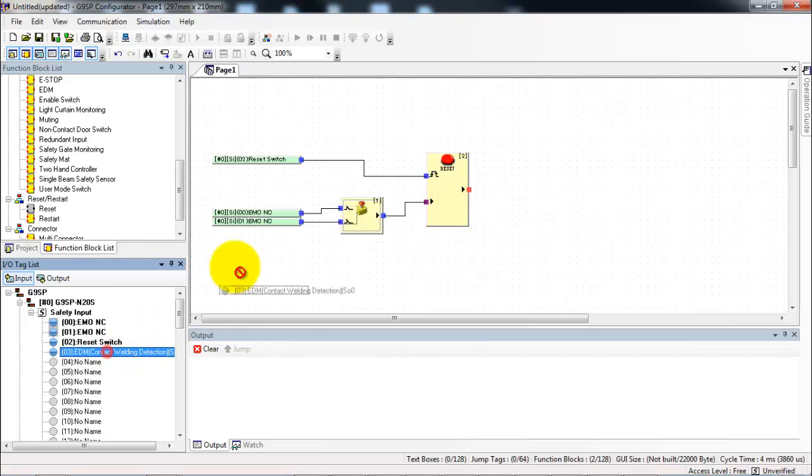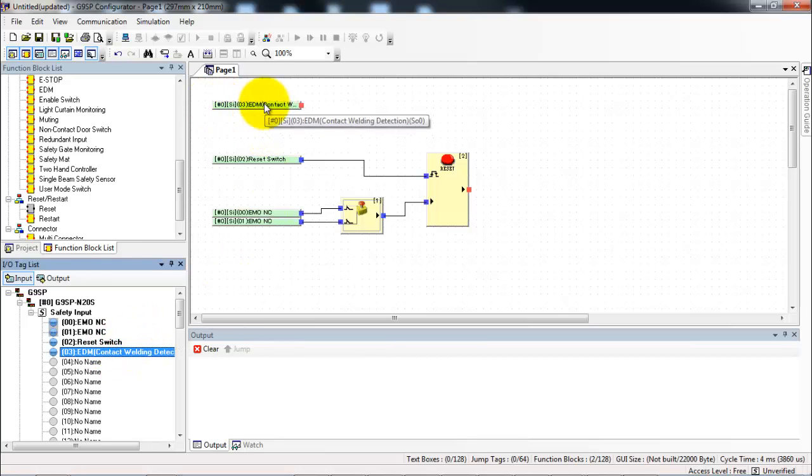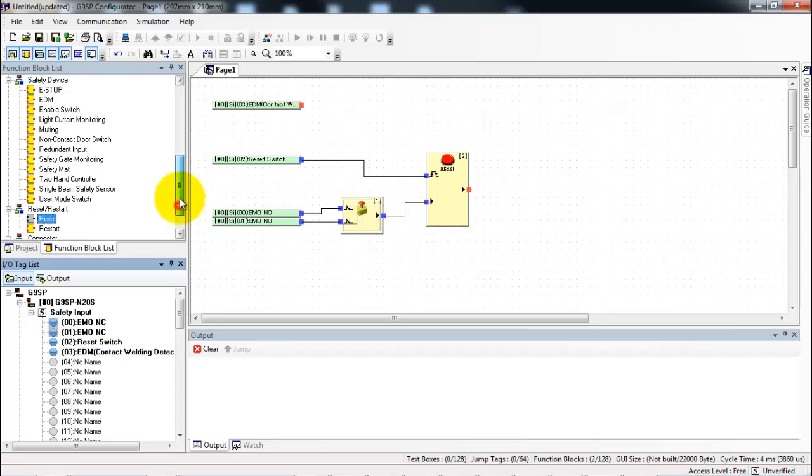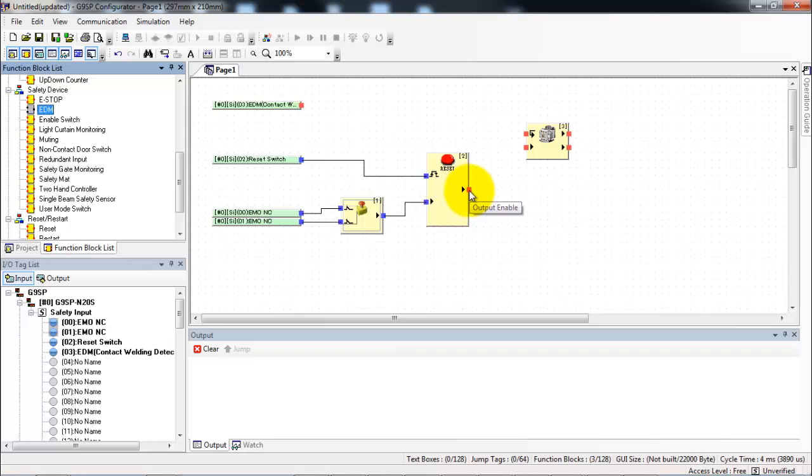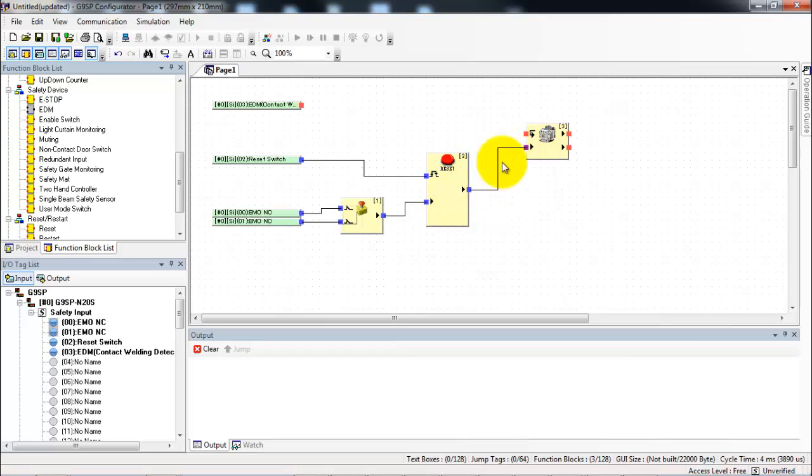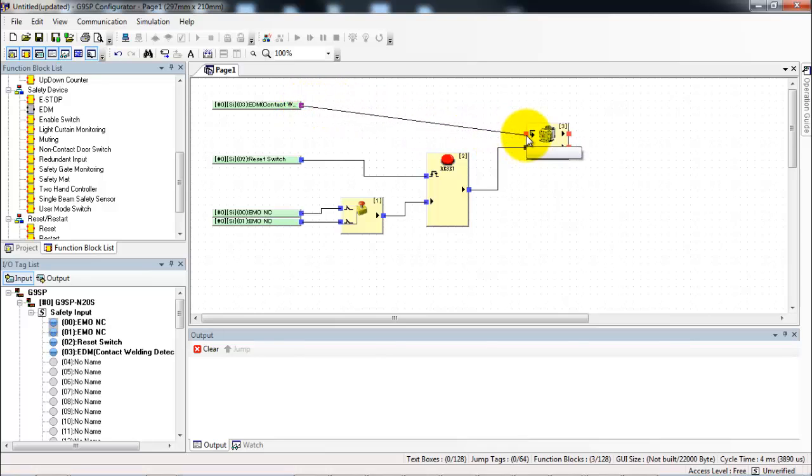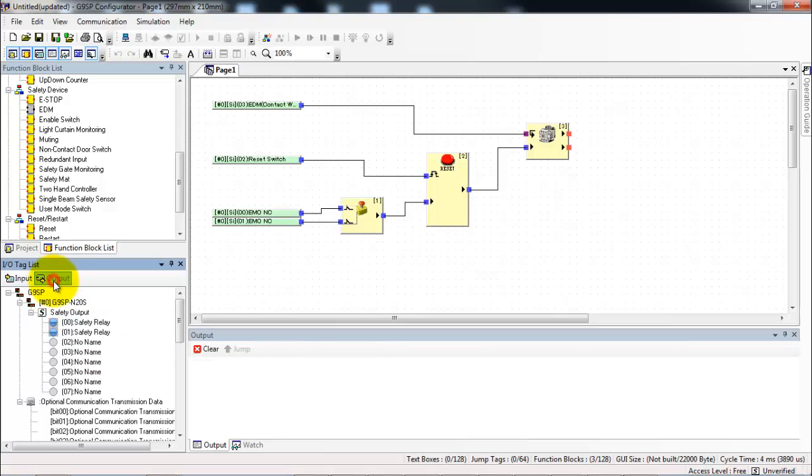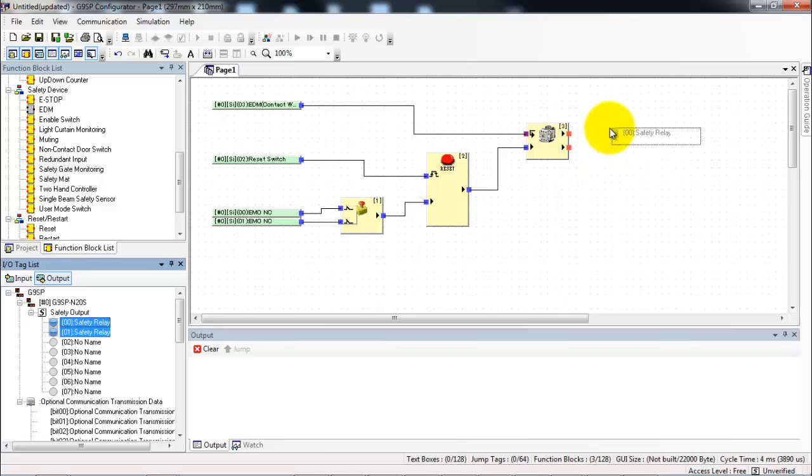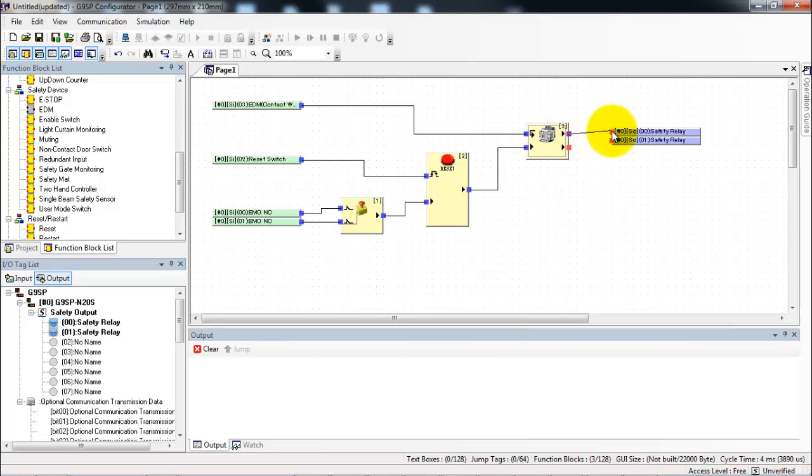Lastly we need to do our weld check. So I drop in my EDM contact and I grab the EDM function block. It stands for external device monitoring. Create a wire from the reset to the EDM and from the EDM input to the function block. Lastly I go to my output tab and grab my two safety relay outputs and I wire them from the output side of the EDM circuit to those outputs.